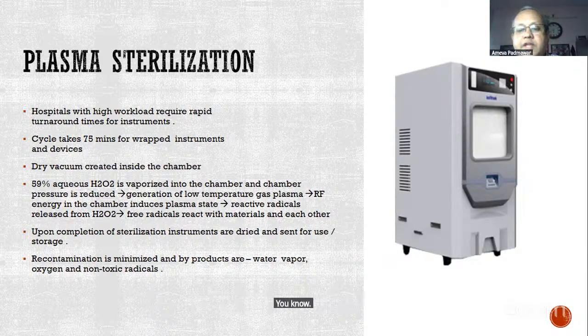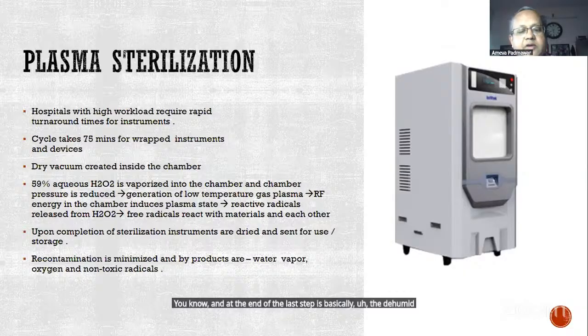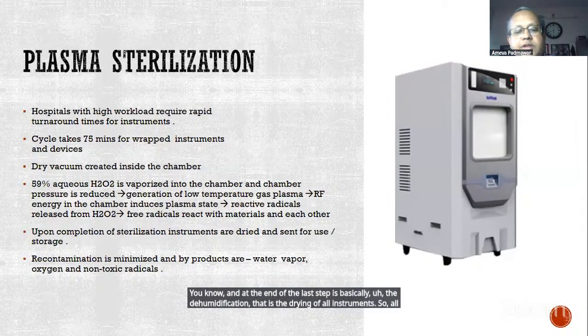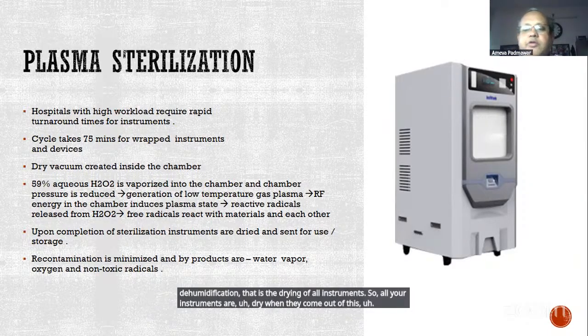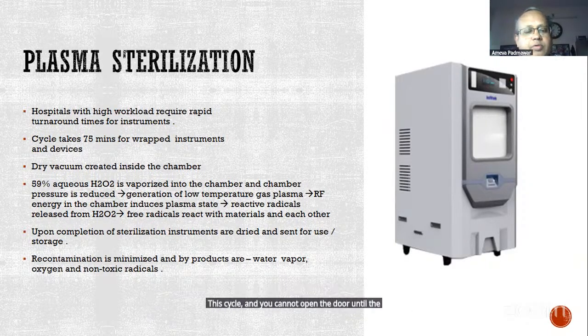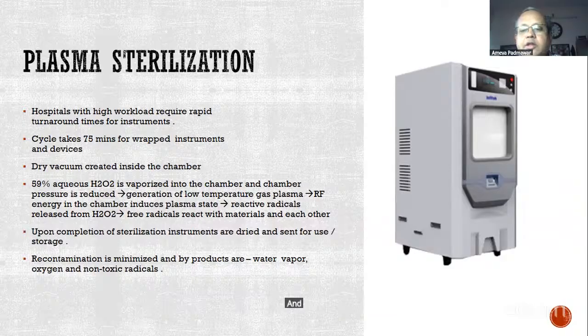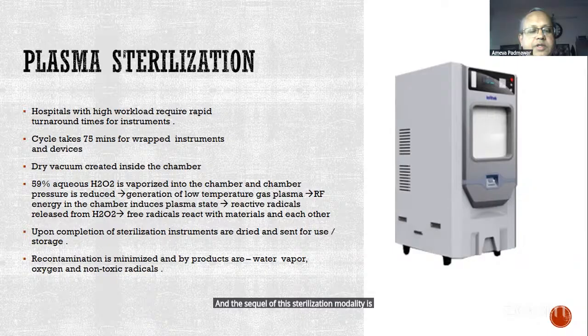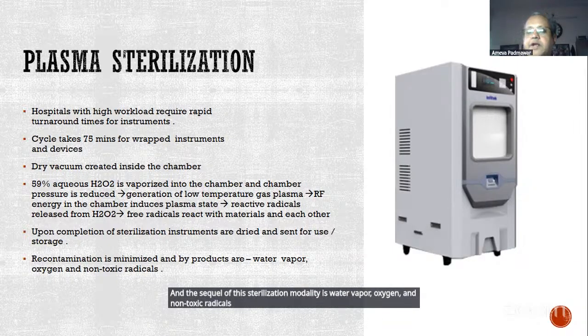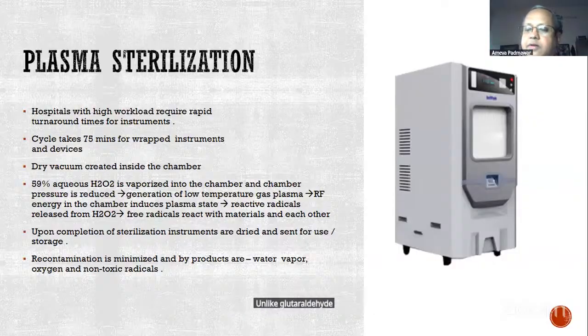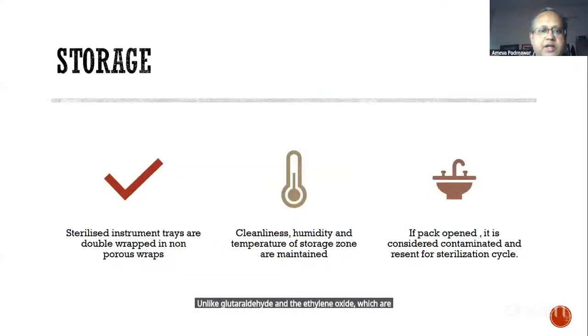And the last step is basically the dehumidification, that is the drying of all instruments. So all your instruments are dry when they come out of this cycle, and you cannot open the door until the cycle is over completely. And the byproducts of this sterilization modality are water vapor, oxygen, and non-toxic radicals. So it is environmentally friendly, unlike glutaraldehyde and ethylene oxide, which are biohazards.